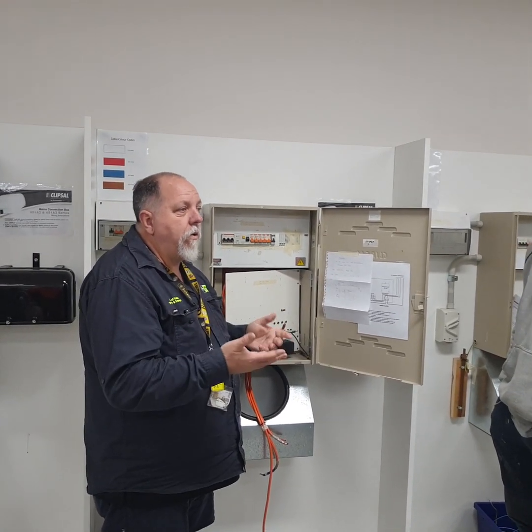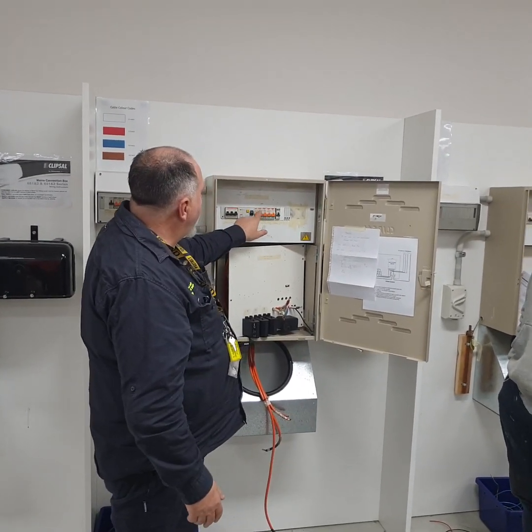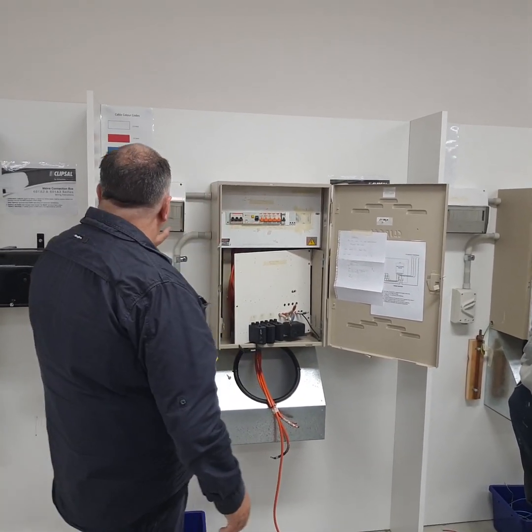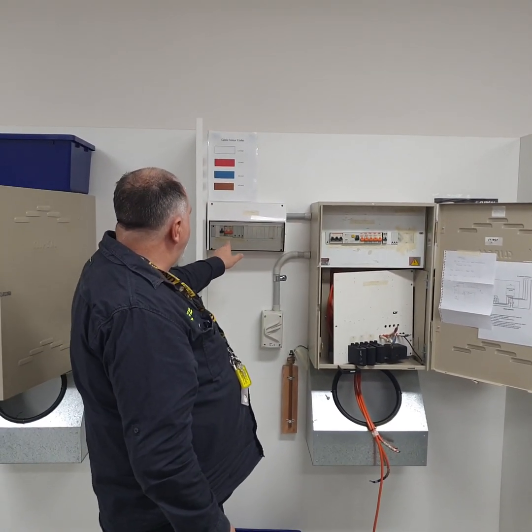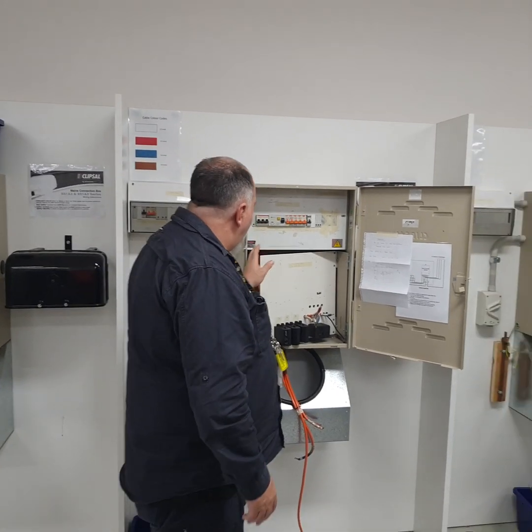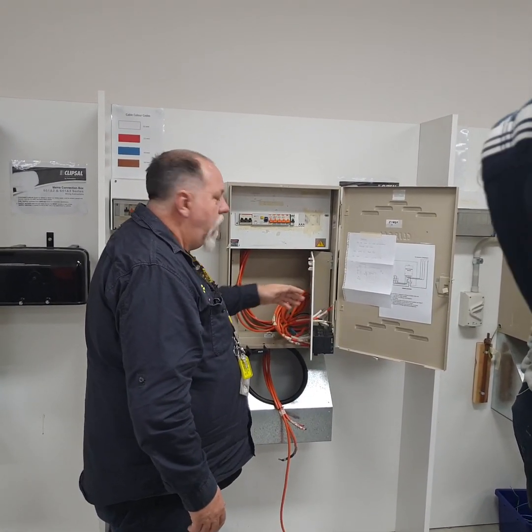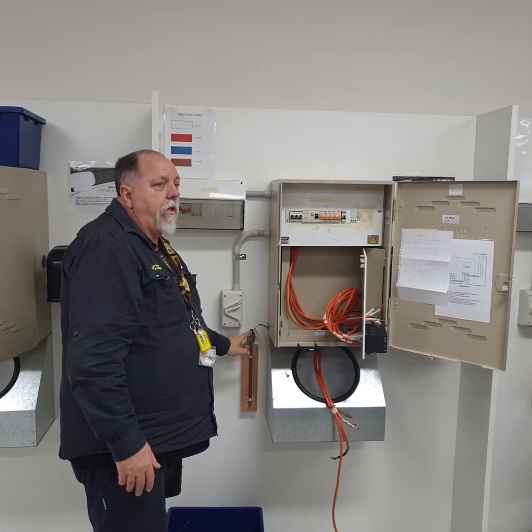We looked at it and it said non-domestic. It was just an incorrect reading, so we brought it back to 1 amp. That means he's now got these all corrected here. The other thing we had over here was another 32 as well. That came back to a 16. And I think, what else was there, Gordon? Yes. Oh, the earth didn't have a cable tie in it either.